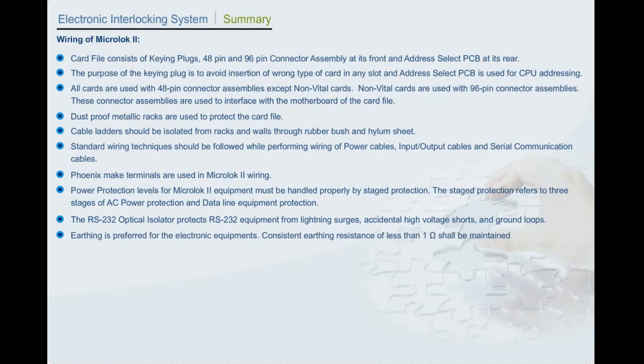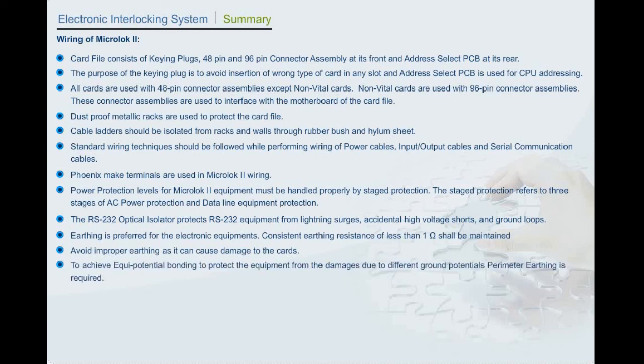Earthing is preferred for the electronic equipments. Consistent earthing resistance of less than 1 ohm shall be maintained. Avoid improper earthing as it can cause damage to the cards. To achieve equipotential bonding to protect the equipment from the damages due to different ground potentials, perimeter earthing is required.